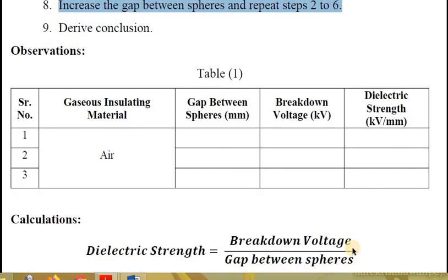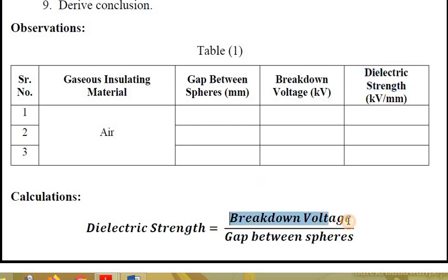After this, increase the gap between the spheres and repeat the steps. Then draw your conclusion. The observation table has 5 columns: serial number, gaseous insulating material (recorded as air), gap between the spheres, breakdown voltage in kilovolts, and dielectric strength — which is the ratio of breakdown voltage to the gap between the spheres. You can take gap values of 5 mm, 10 mm, 15 mm, and so on.